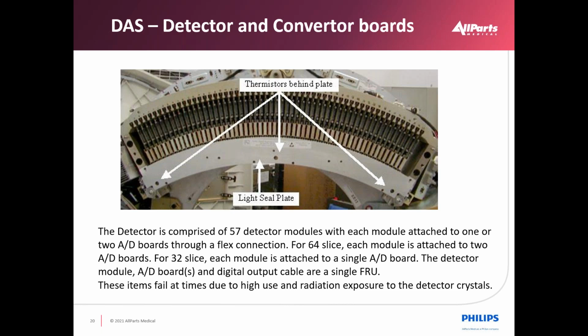So the detector, right behind what you would see is a light seal plate here, is actually the detector elements, which are the crystals. So there are individual crystals. In this case, this detector has the depth of these cards right here, 64 rows going straight back. And each one of those has a separate detector element, aka crystal, feeding a photodiode, and the photodiode then feeding the A to D, which is on these circuit boards. And then A to D then is converted, obviously, to a digital number, and that is then transferred to our data collection hard drives. So that being said, as you can tell, there's 57 detector module detectors here, but 64 depth, and they represent about 768 channels total across this array.